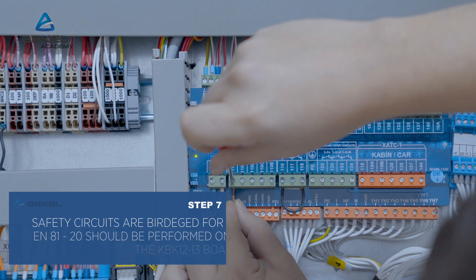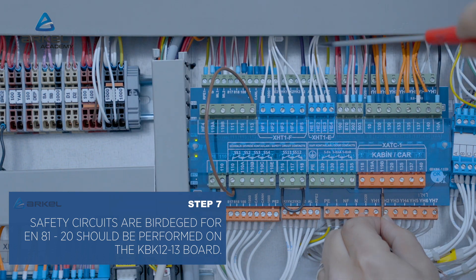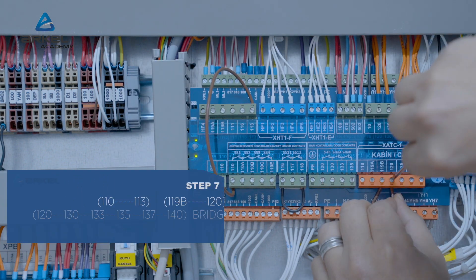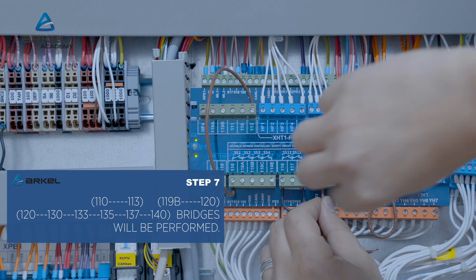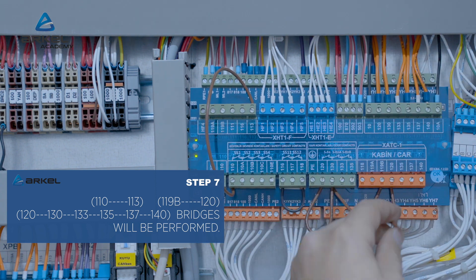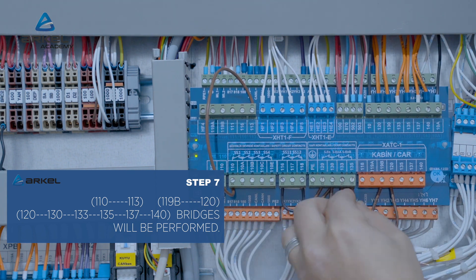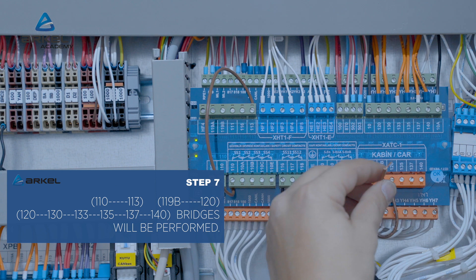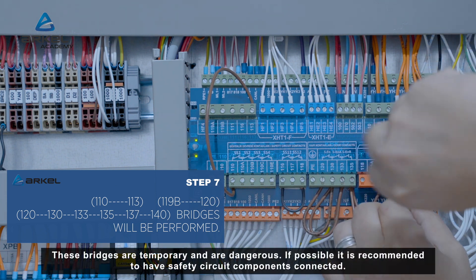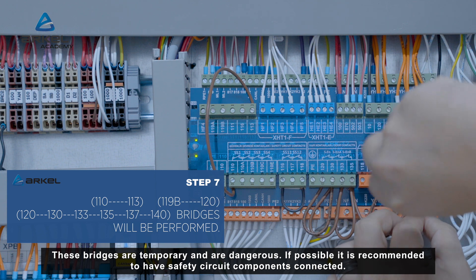Safety circuits are bridged. For EN 81-20, this should be performed on the KBK 12 to 13 board: 110 to 113, 119B to 120, and 120 to 130 to 133 to 135 to 137 to 140 bridges will be performed. These bridges are temporary and are dangerous. If possible, it is recommended to have safety circuit components connected.